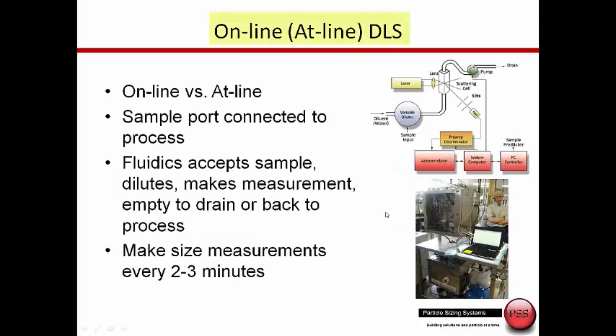Another unique capability of particle sizing systems is the ability to do dynamic light scattering online or at-line. Here we take the sample into a variable diluter. The sample comes in, we dilute the sample, bring it into the cell where we take the measurement, stop the flow, take the measurement, clean up and do another measurement. This is useful when dealing with very high value samples.